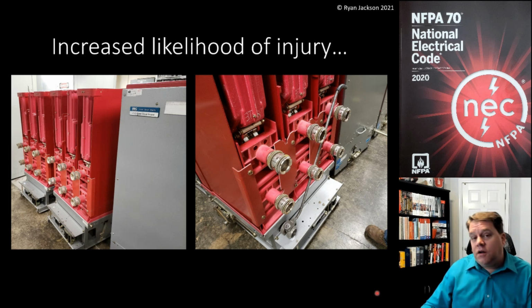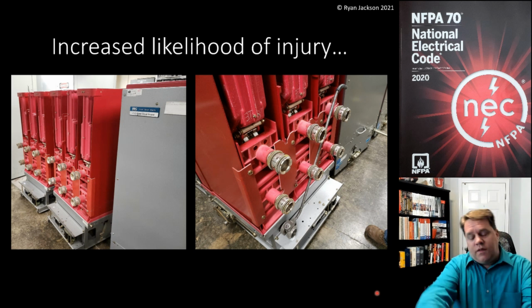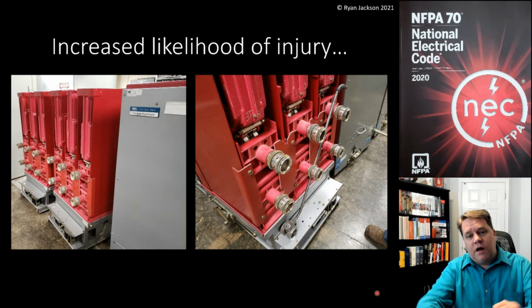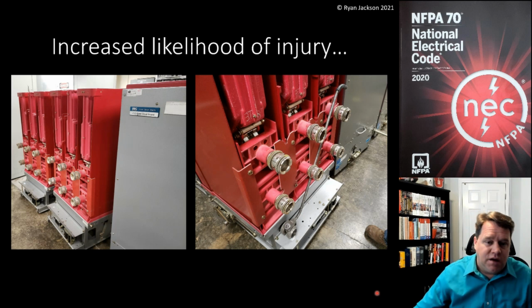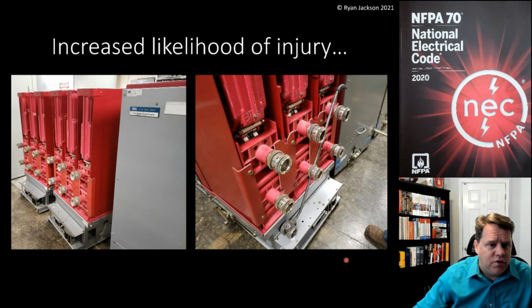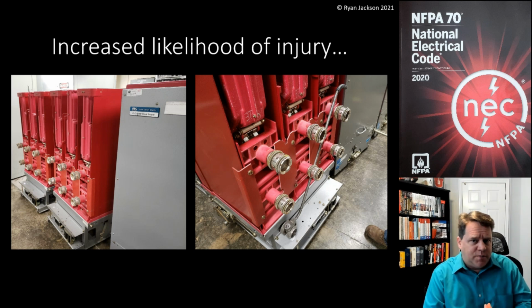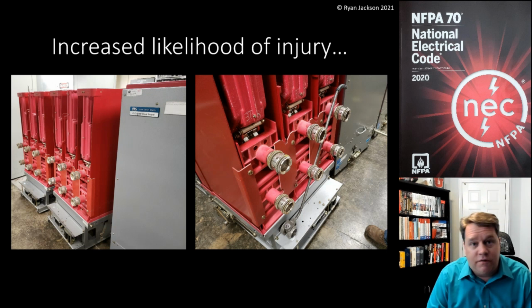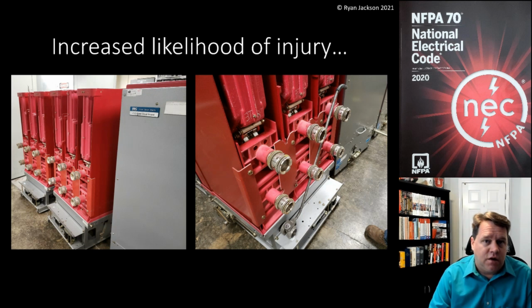So, you talk about an increased likelihood of injury. When they were taking that circuit breaker out, if they had jostled it even slightly, you can see that this bar might have fallen line to line and we would have had a 12,470 volt arc flash happening. So that would be an increased likelihood of injury. So if I'm in the limited approach boundary, or if I'm doing something that has an increased likelihood of an injury, then I need to create and verify an electrically safe work condition before performing the task.